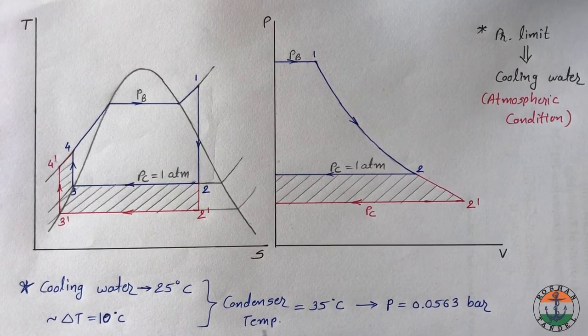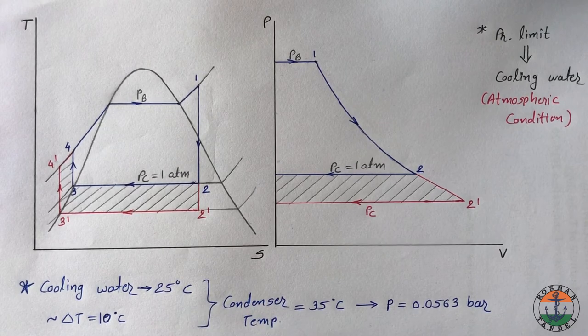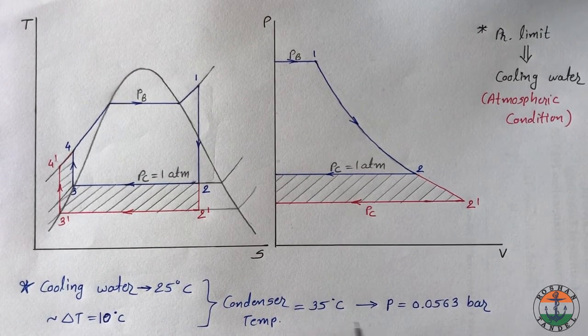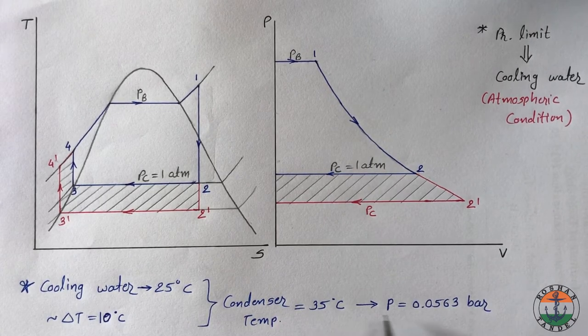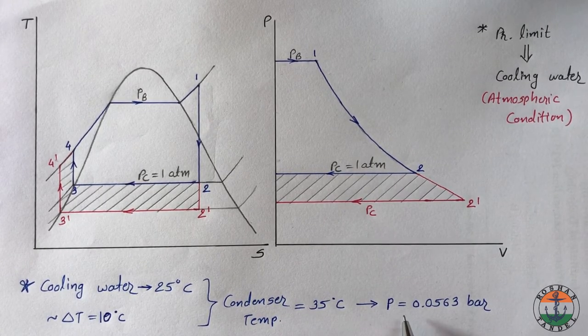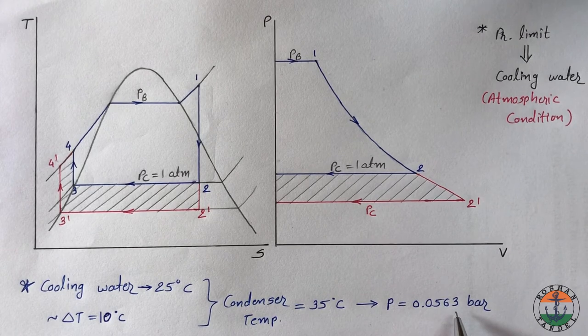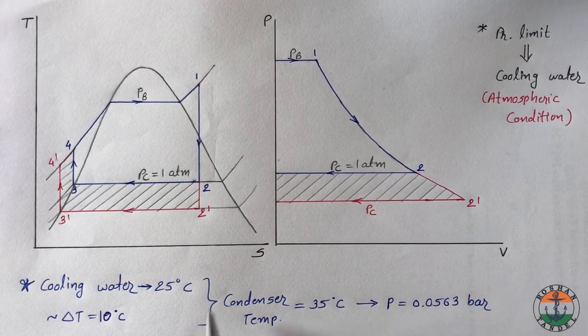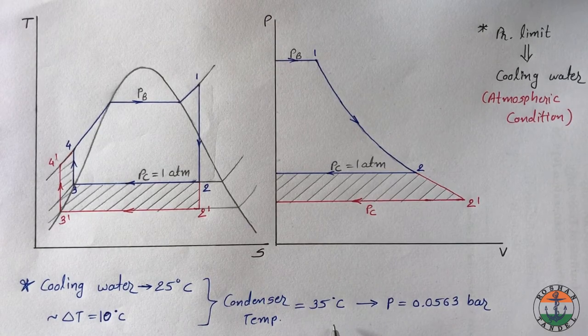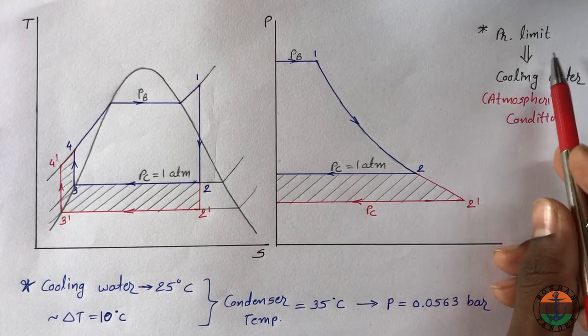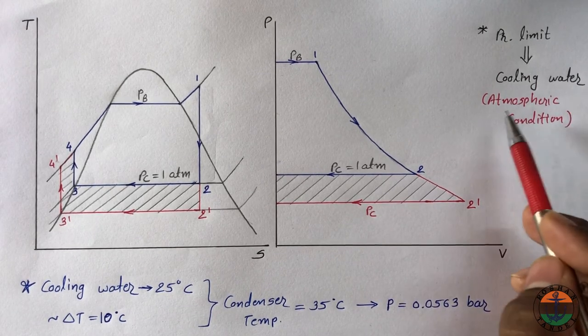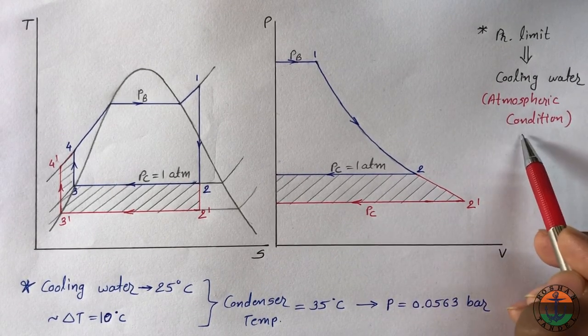To transfer the heat there must be a temperature difference of around 10 degree Celsius. So you have to maintain condenser temperature at about 35 degree Celsius. At this temperature corresponding saturation pressure is 0.0563 bar. This is how condenser pressure limit is decided. You can say that pressure limit in the condenser is dependent on cooling water or atmospheric condition.